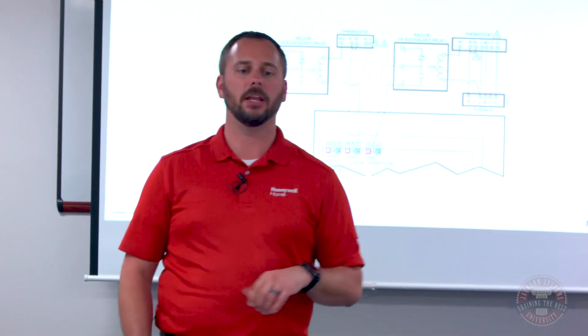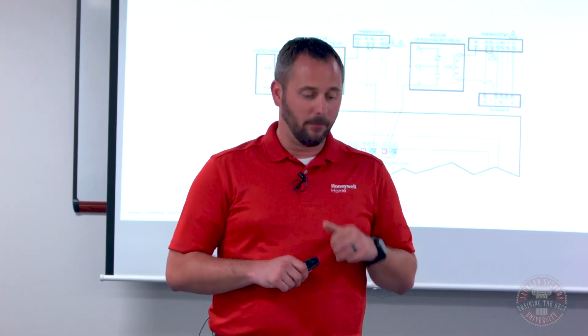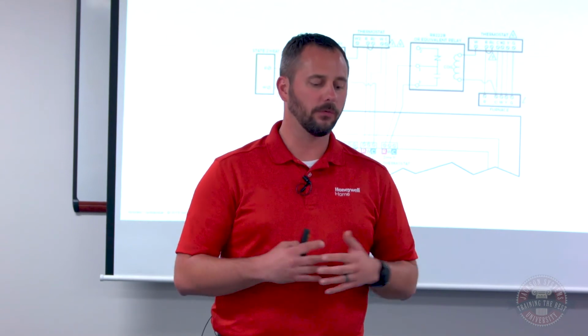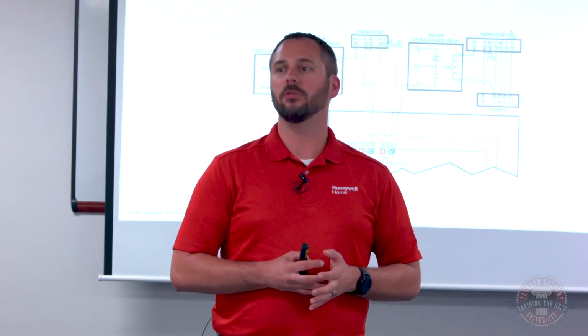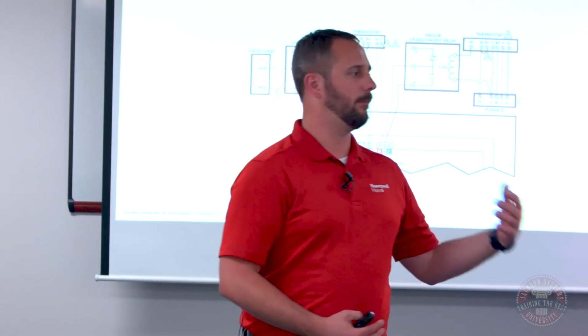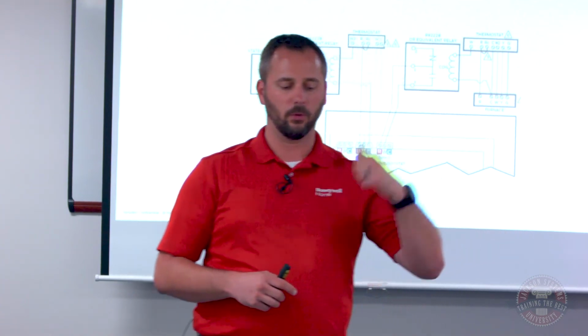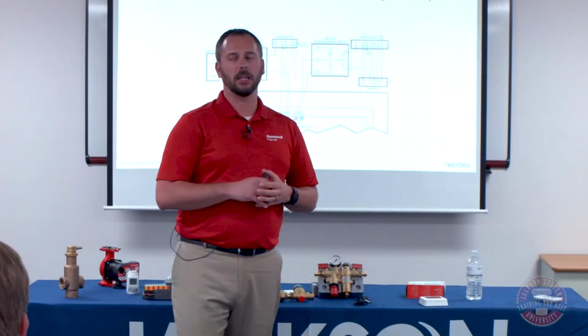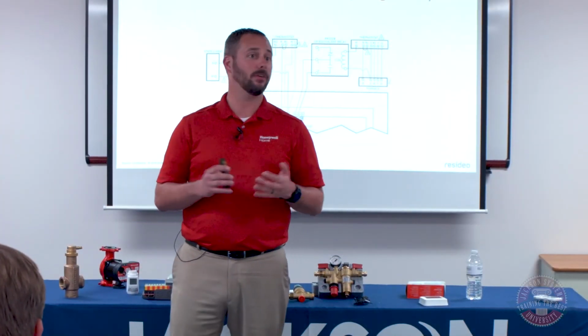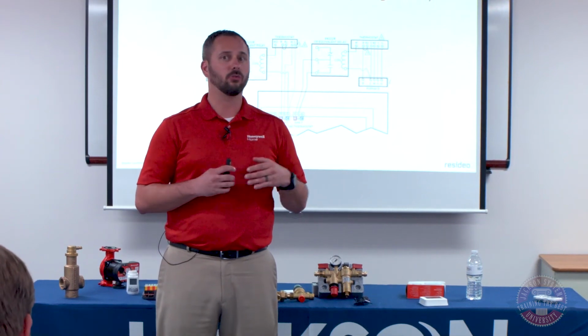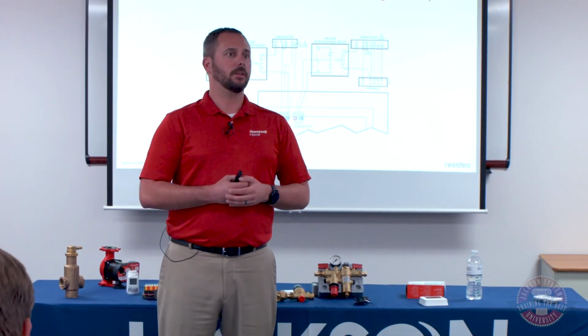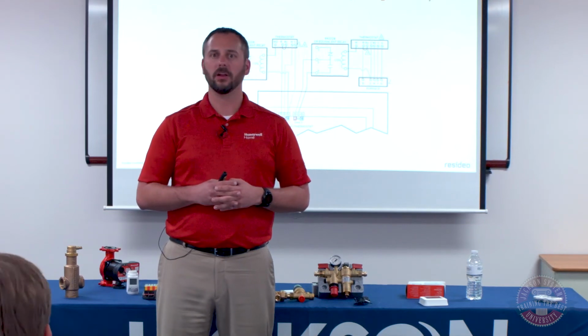The other thing, and I threw this in here more or less for reference, the next 2 slides. So the first one is showing you what do you do if you've got 2 stages of heat. So let's say your first stage of heat is radiant and your second stage of heat is a furnace or a baseboard or a fan coil unit or whatever you could dream up. This is 2 different ways you can do it. These are described in much more detail in our wiring diagram reference guide that we've put together. But depending on what is the secondary stage of heat, there's different ways to wire it up. Both of these applications require a relay, but these are simplistic relays and the wiring is pretty straightforward.